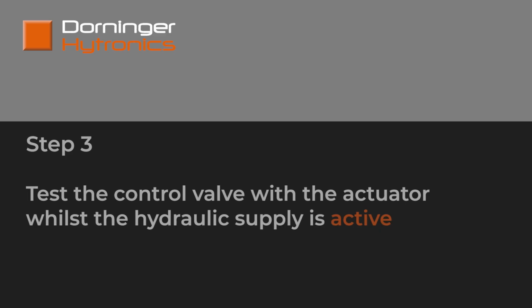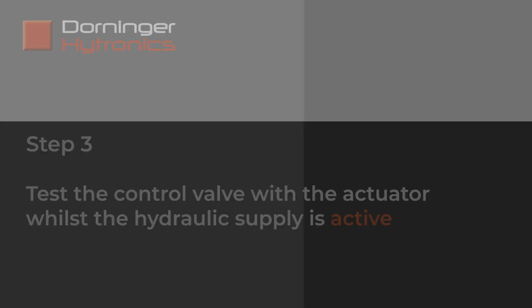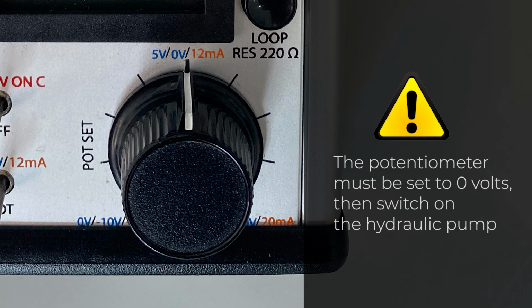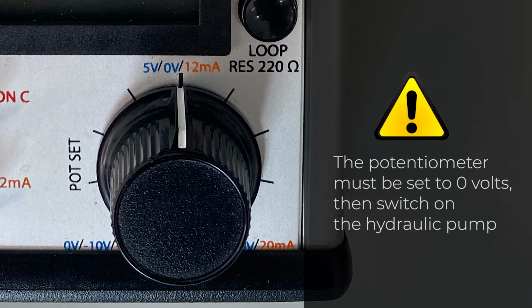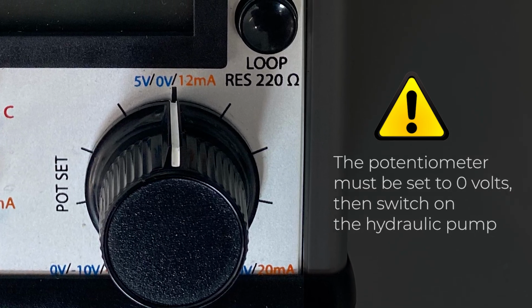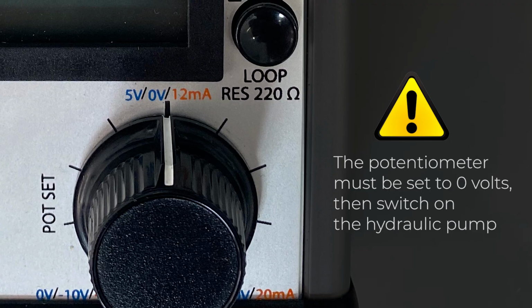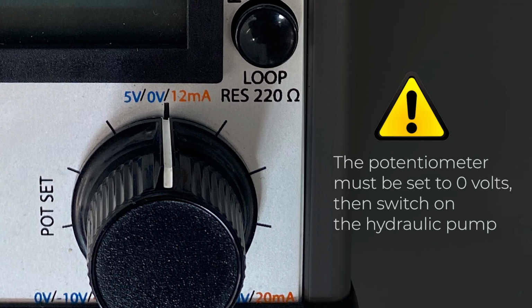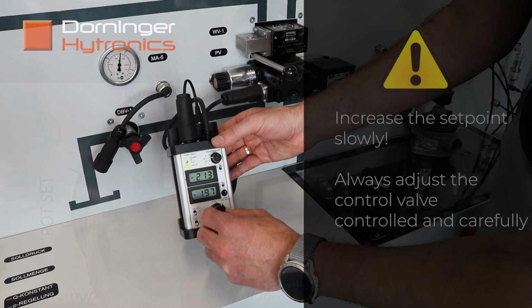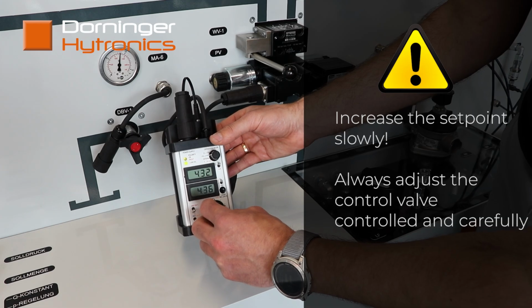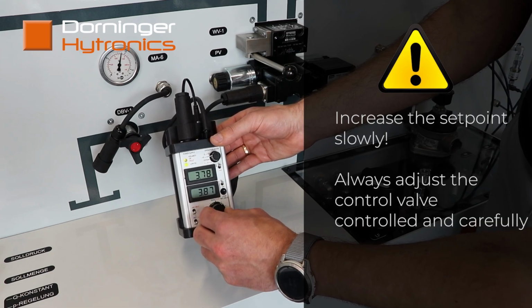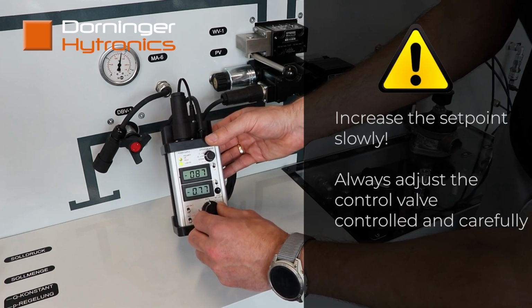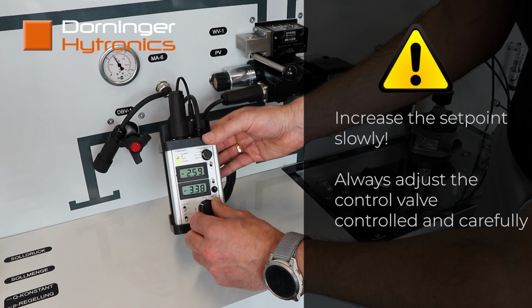In the final step, we test the control valve with the hydraulic supply active. First, the hydraulic pump is switched on and the procedure shown in the previous test is repeated. Make sure that the potentiometer is set to 0 volts at the start of the test. Initially, the potentiometer should be moved slowly. This allows the function to be checked in a controlled and safe manner.